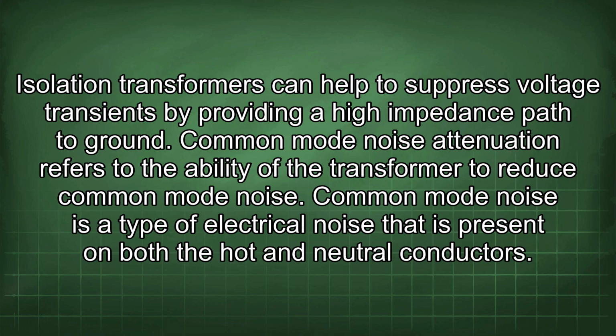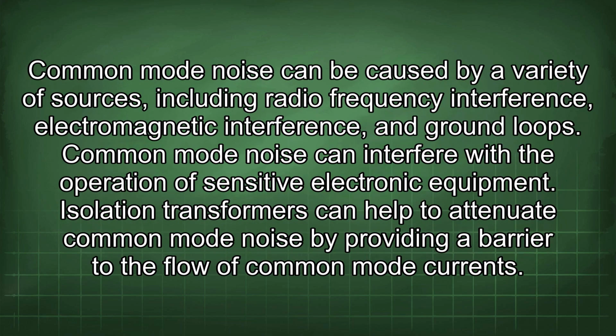Common mode noise attenuation refers to the ability of the transformer to reduce common mode noise. Common mode noise is a type of electrical noise that is present on both the hot and neutral conductors. Common mode noise can be caused by a variety of sources, including radio frequency interference, electromagnetic interference, and ground loops. Common mode noise can interfere with the operation of sensitive electronic equipment. Isolation transformers can help to attenuate common mode noise by providing a barrier to the flow of common mode currents.